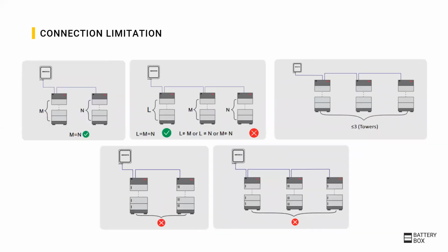For the parallel connection, there are also some limitations. Up to 3 towers can be connected in parallel. For this, all towers need to have the same module quantity and thus the same voltage. Furthermore, it is not possible to mix HVS and HVM towers in a parallel system. And again, please refer to the compatibility inverter list to check which configurations will work with which inverter.